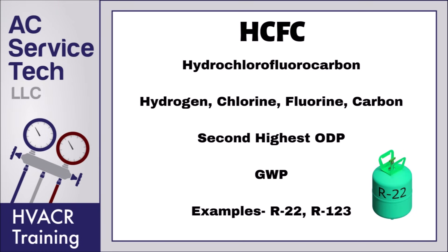HCFC refrigerant is hydrochlorofluorocarbon, made up of hydrogen, chlorine, fluorine, and carbon. It has the second highest ODP and also contributes to global warming. Some examples are R22, which was widely used in residential and commercial air conditioning and refrigeration, and R123, which was a retrofit for R11 and R113 for chillers.